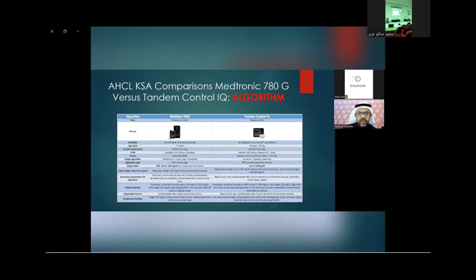And there are parameters that still need to be set in Tandem, like the basal insulin rate, the carb ratio, the insulin sensitivity factor, and the weight. While in Medtronic, the only things that need to be set are really the carb ratio and the active insulin time. The active insulin time is fixed in Tandem, and it can be changed in Medtronic. So as you can see, there are differences between the pump itself, between the sensor, and between the algorithm. And it's your decision and the patient's decision to choose which one of them.